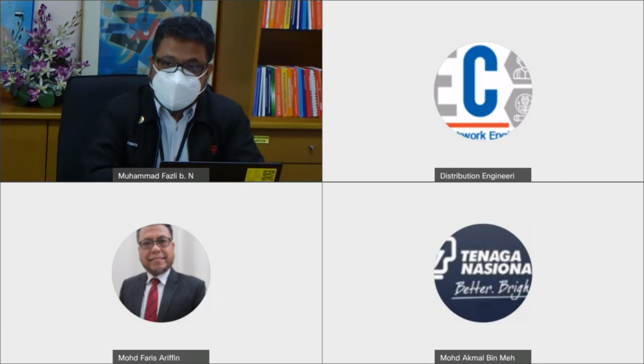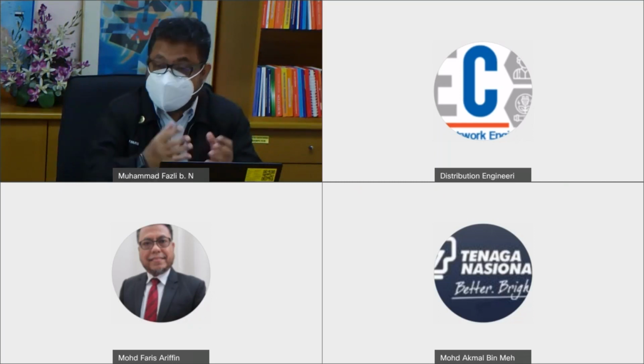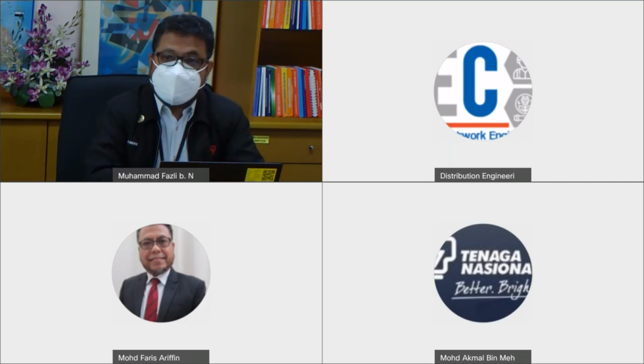And for example, if you have these micro cracks in the porcelain insulator, the dielectric strength of the porcelain insulator is already deteriorating. You won't be able to see all these micro cracks because they are internal. So that is why we prefer to use glass insulator, because if the dielectric is already over the strength, it will rupture. That is simple for us to detect. But for porcelain, it is very hard for us to detect the micro cracks.